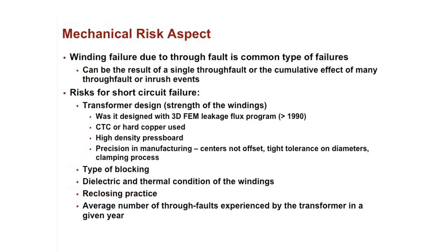This is the strength of the winding, the strength of what it can take. Normally, if it was designed after 1990, the computers became so much better that it could be designed with a 3D finite element tool. And if it was designed with that, normally the short circuit forces are taken care of. If it was designed before 1990, then it was designed more with hand rules and paper calculations. For those, the transformers normally cannot take present day short circuit forces. So that's one of the first things we look at.